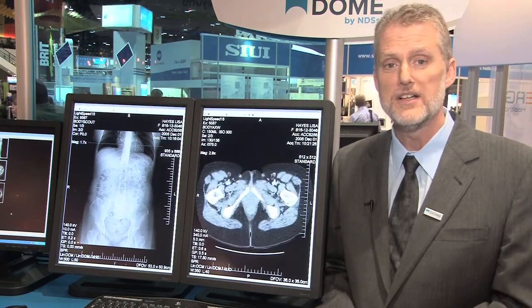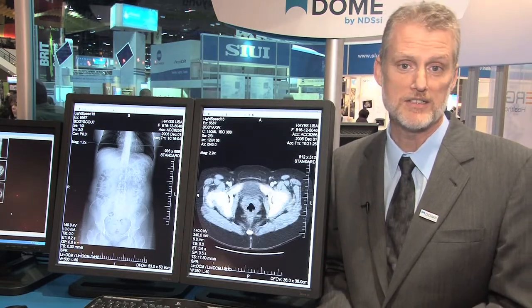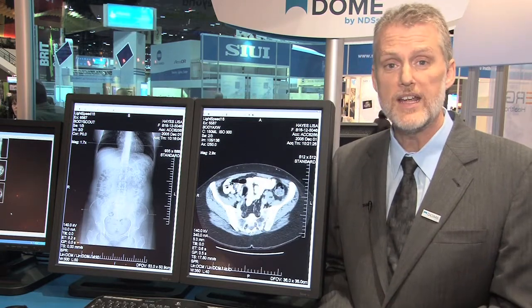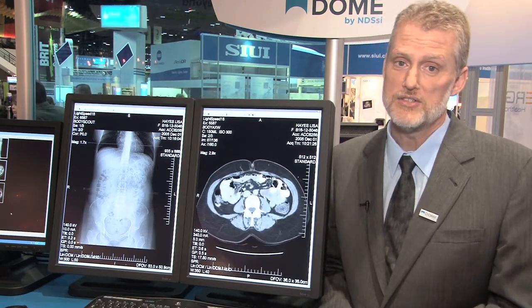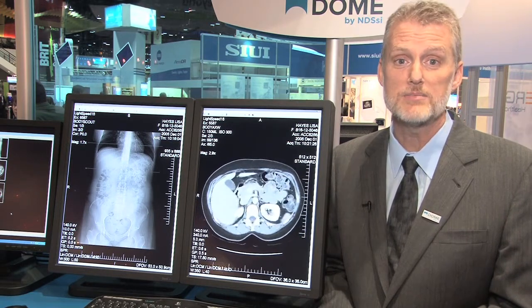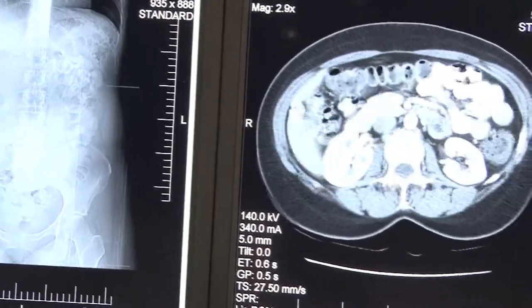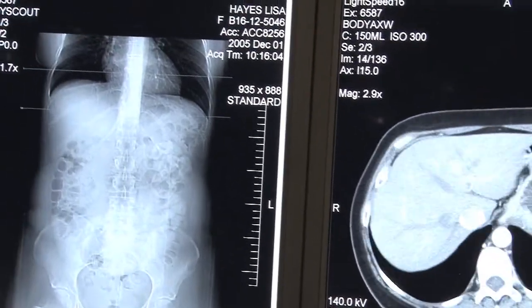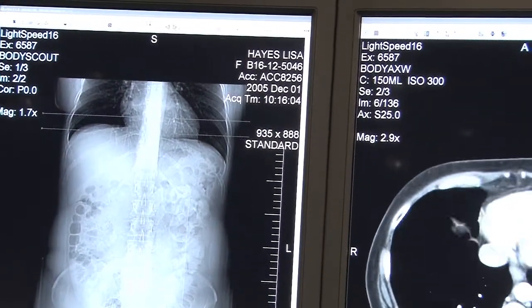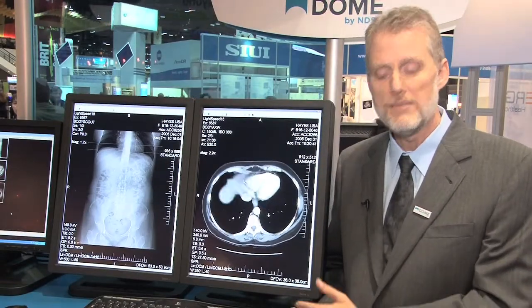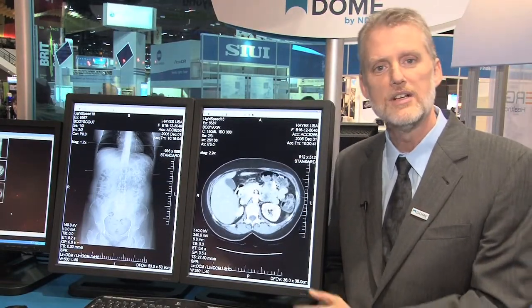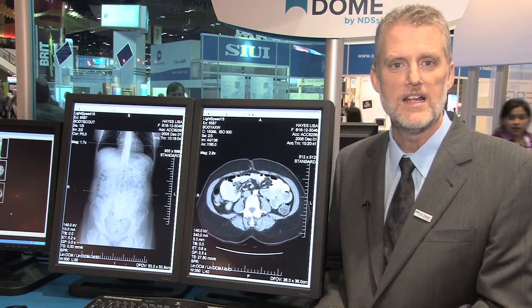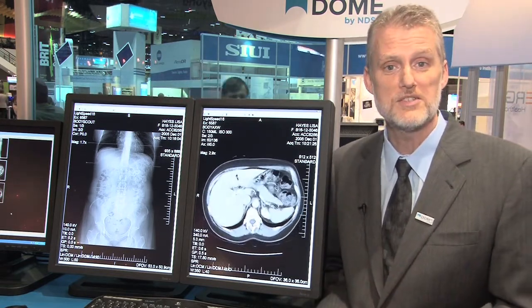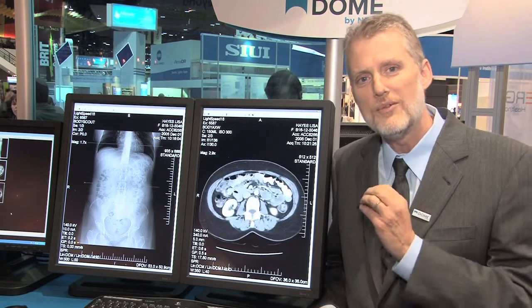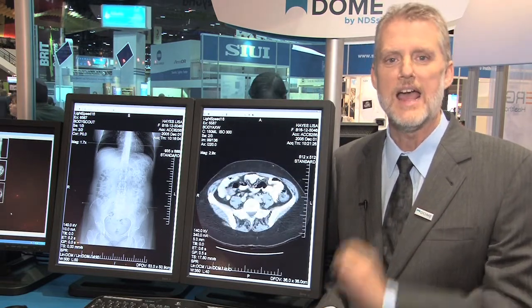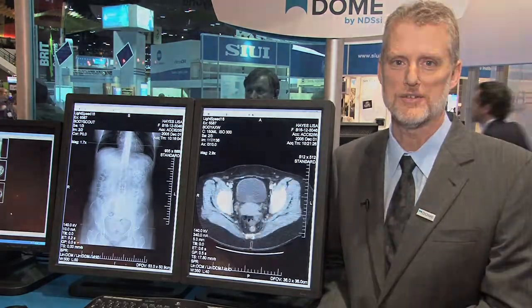Well, earlier this year, a research paper done at MD Anderson Medical Center gave us some new data. MD Anderson has used Dome displays for a very long time, and they had displays that were as much as 10 years old, 30,000 hours of operation. And they demonstrated that there was no difference in the conformance and calibration from those very early displays 10 years ago to very current displays. That new displays were behaving just as well as the older displays. That in fact, it was the right way to calibrate your display. Absolutely, precisely in the factory.